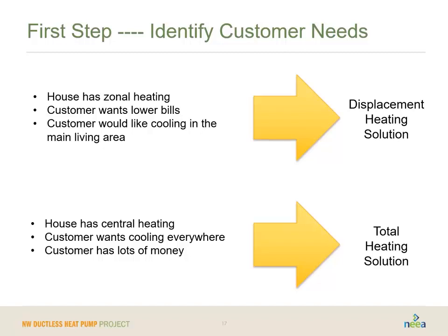If the customer has a high need to reduce their bills, if that is one of their driving impetuses, and the consumer would also like cooling, at least in the main living area, and that's a high enough priority, but maybe they don't need it in every room of the house. If they can trigger those three, then displacement heating and cooling is going to be an ideal solution for those homeowners. If, however, the home only has central heating and the customer wants cooling everywhere, and the customer is not quite as concerned or driven by either first cost or their utility bills, then you can start thinking about a total heating solution or a total system replacement and upgrade.